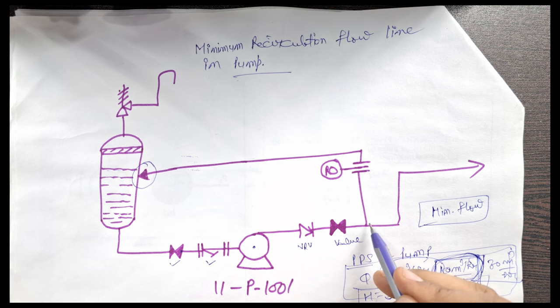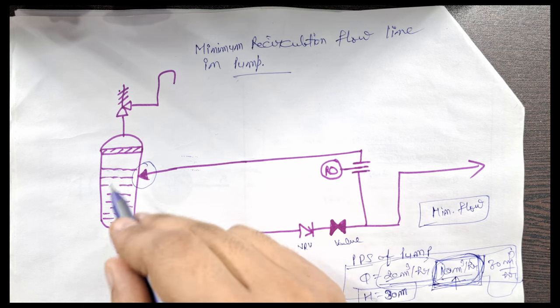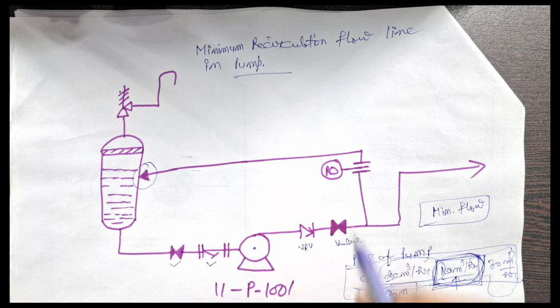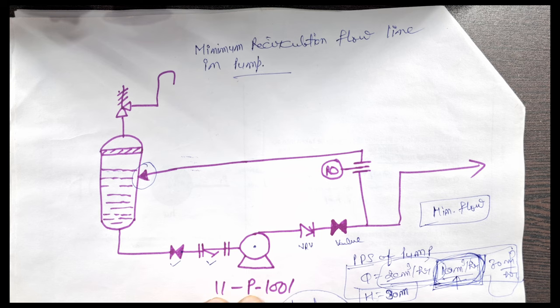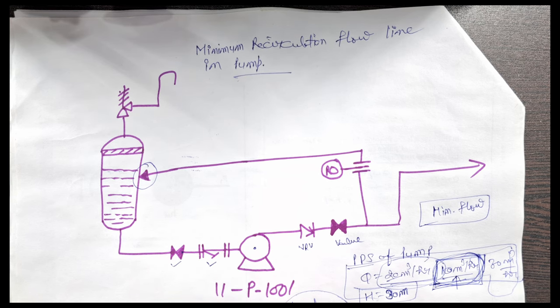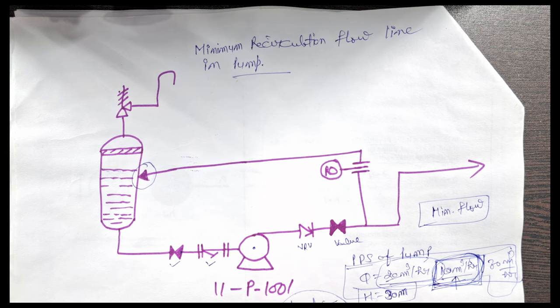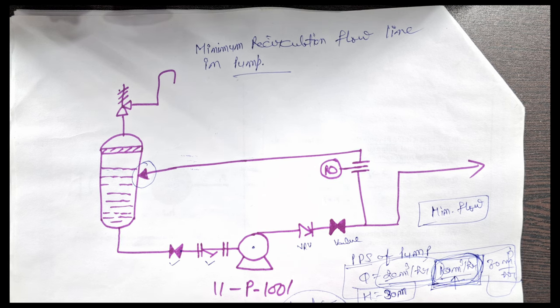To protect your pump, we provide the minimum recirculation line. It also helps protect the pump from deadhead. Deadhead means protecting your pump from dry run — otherwise your pump motor could be damaged and your pump could overheat. Deadhead occurs when your pump goes towards zero flow rate, at which point the shut-off head occurs.